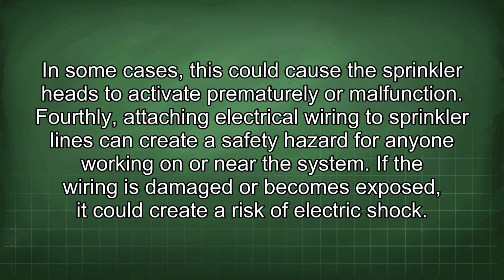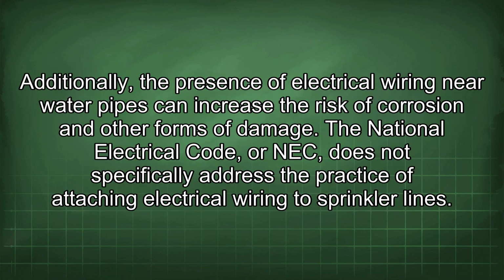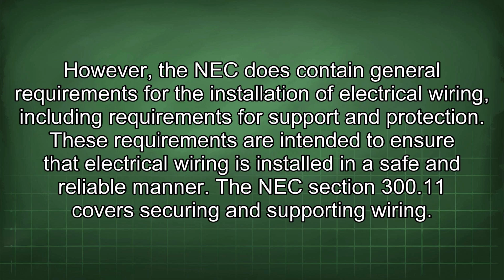Fourthly, attaching electrical wiring to sprinkler lines can create a safety hazard for anyone working on or near the system. If the wiring is damaged or becomes exposed, it could create a risk of electric shock. Additionally, the presence of electrical wiring near water pipes can increase the risk of corrosion and other forms of damage. The National Electrical Code, or NEC, does not specifically address the practice of attaching electrical wiring to sprinkler lines. However, the NEC does contain general requirements for the installation of electrical wiring, including requirements for support and protection. These requirements are intended to ensure that electrical wiring is installed in a safe and reliable manner.